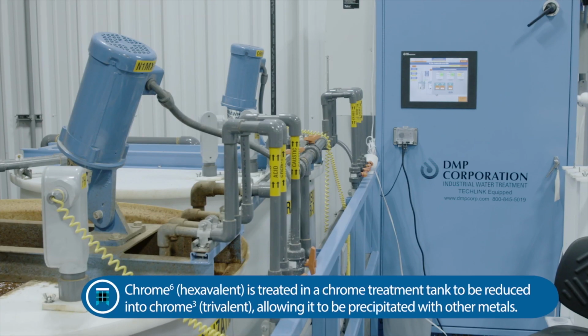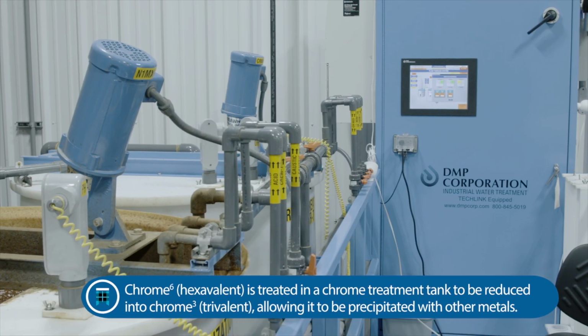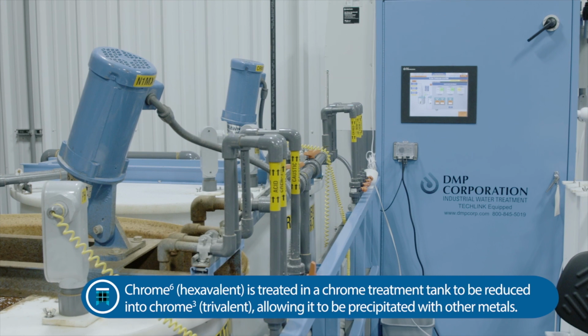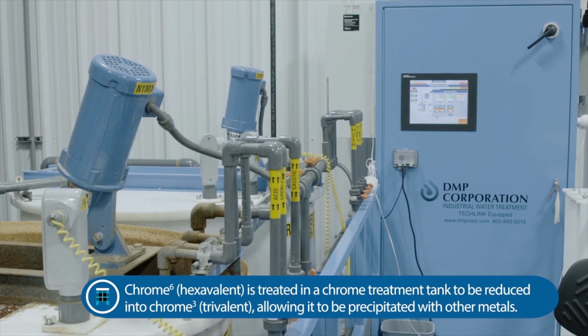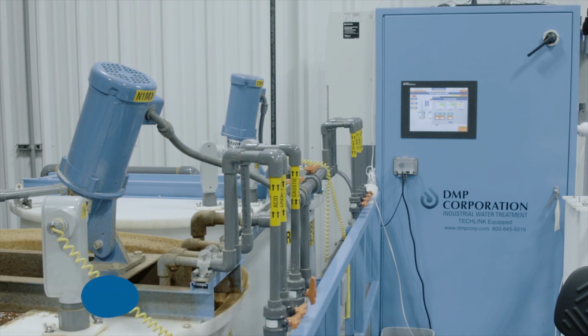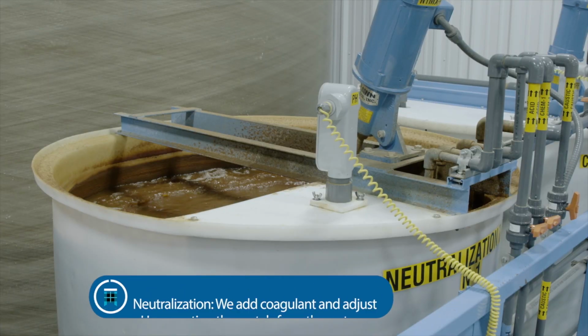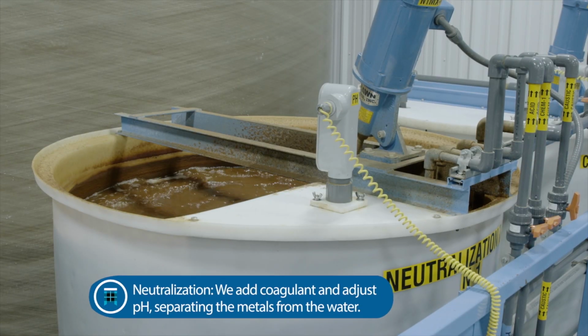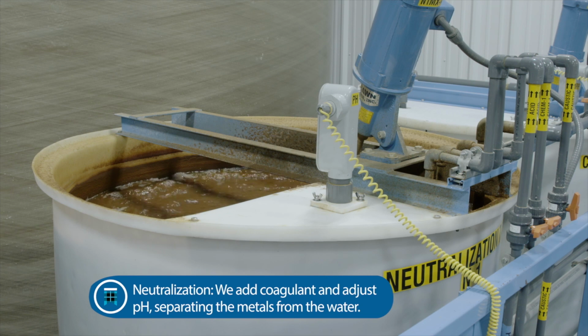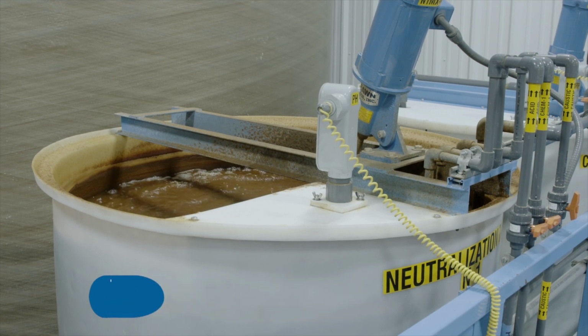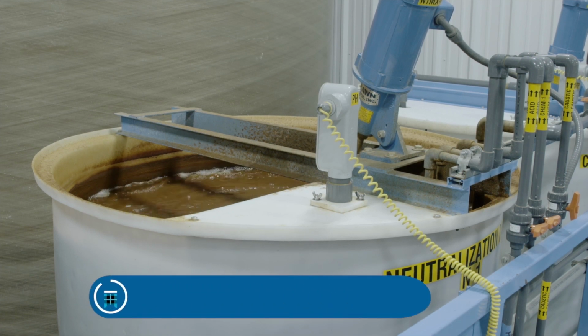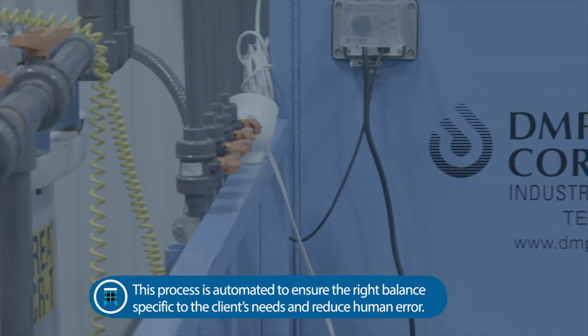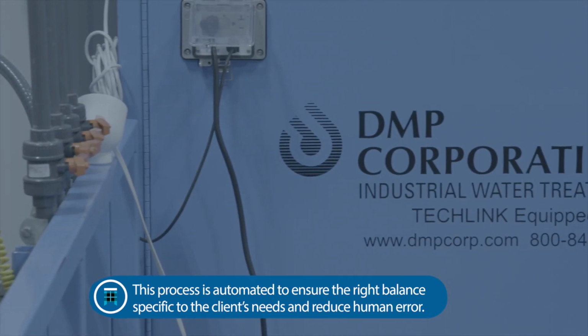Dissolved metals and metal salts are reduced to neutral hydroxides. We add coagulants and adjust pH, separating the metal hydroxides from water. This process is fully automated to provide optimum results for each customer's operation.